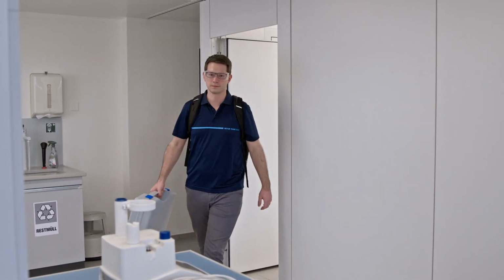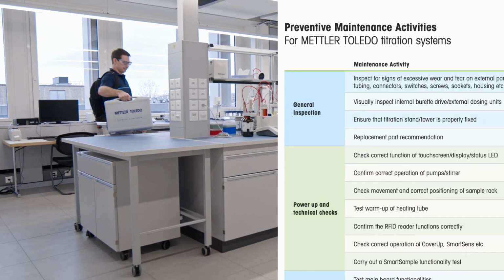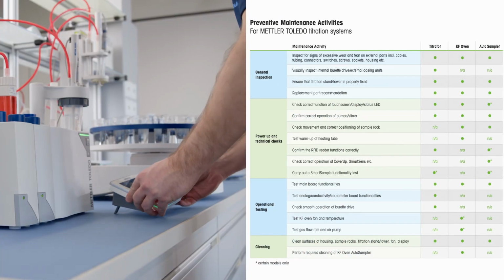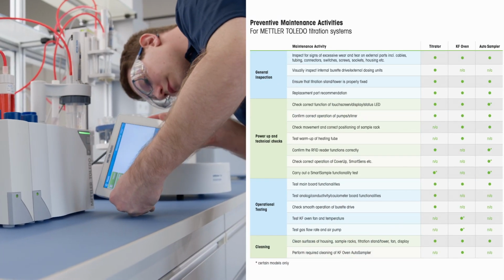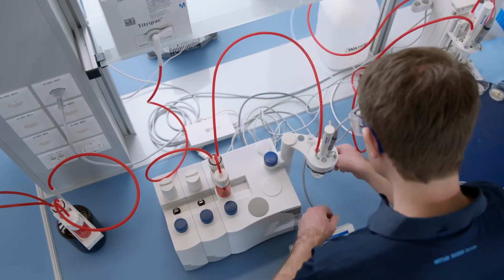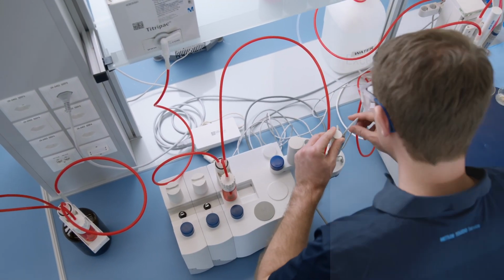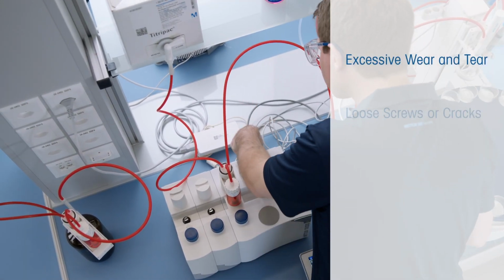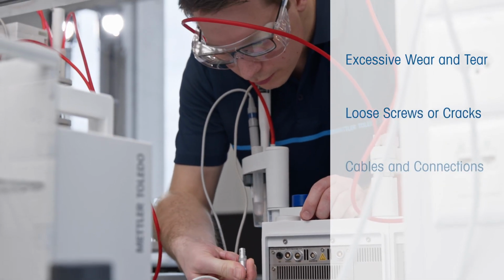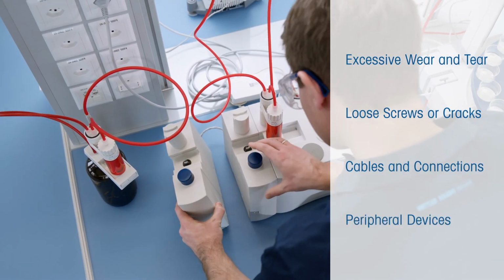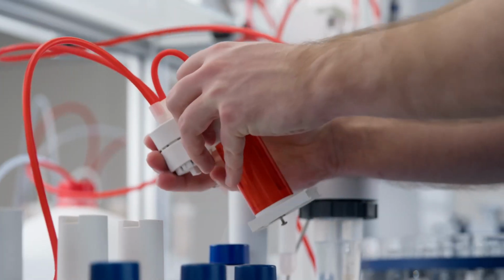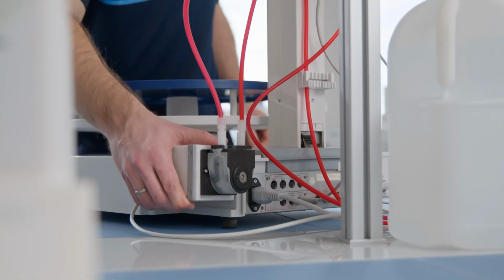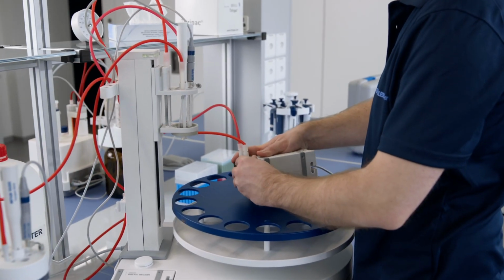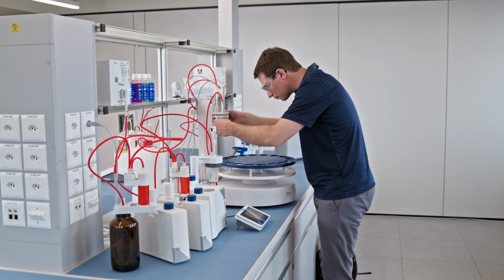METTLER Toledo's preventive maintenance service goes far beyond simple cleaning. Our factory-trained service technicians thoroughly investigate the entire system. They look for signs of excessive wear and tear, loose screws and cracks, loose cables and connections, and check peripheral devices such as burettes, stirrer, pumps, auto sampler, and more depending on your system configuration.